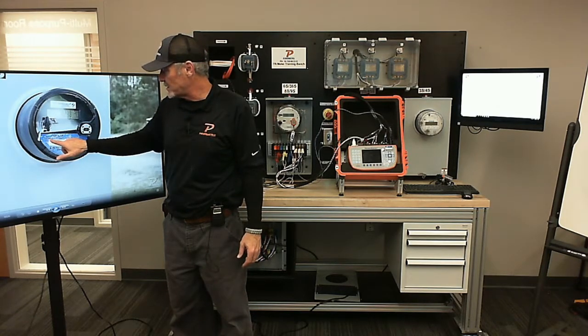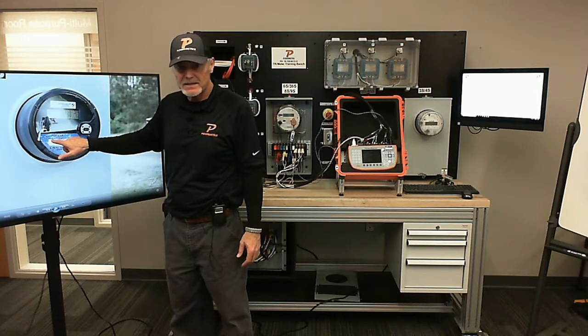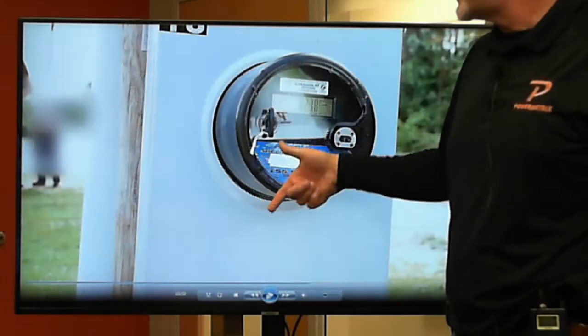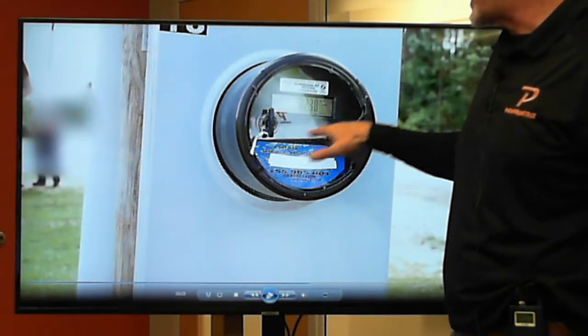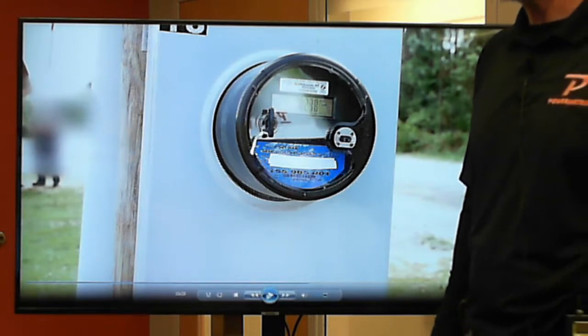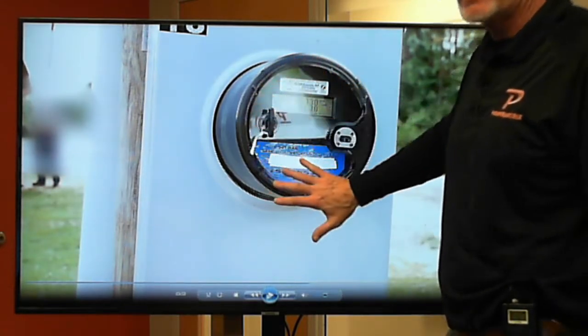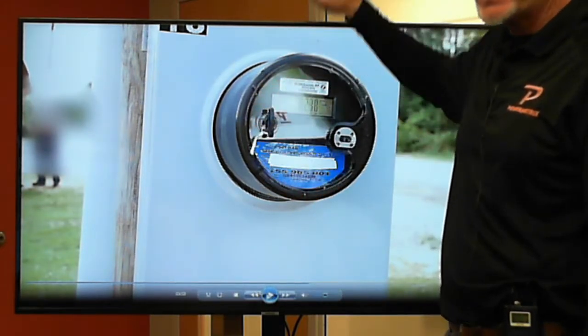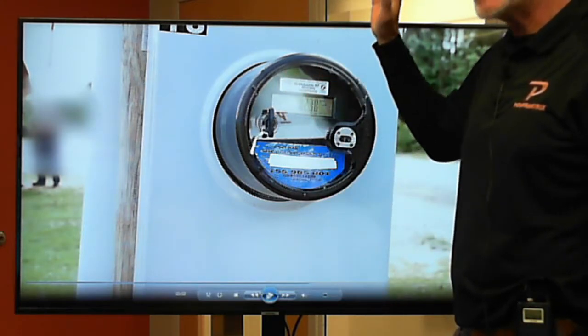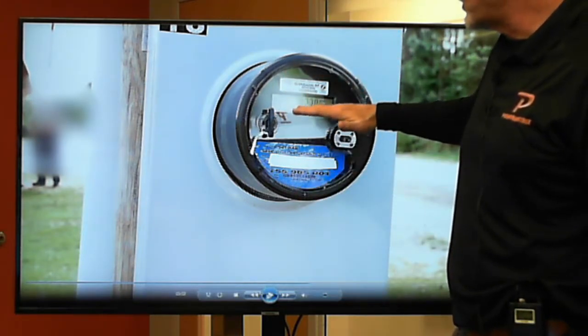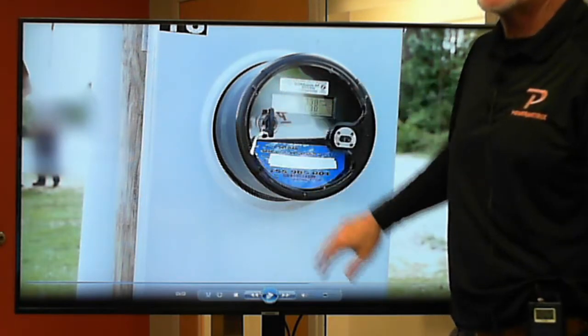And it also says on here it's a form 9S or 8S. If it was a delta site, then it would be an 8S, but this is a Y site, so it's a 9S, so it's functioning as a 9S. All that you just get off of here, okay, before you've even got started. So you've done an inspection of the pole, inspection up top, come down. Now you've gotten to this point where you've gathered information off of that meter before you've actually started the test as well.